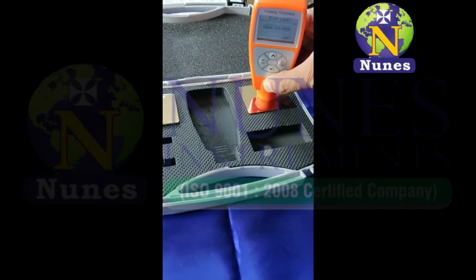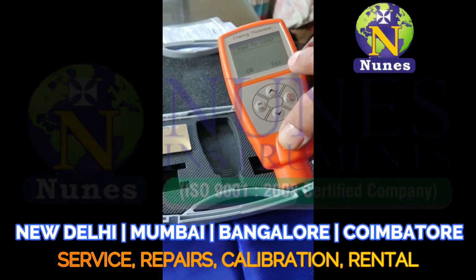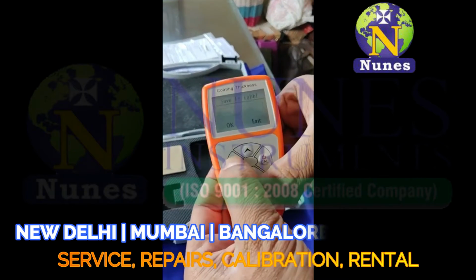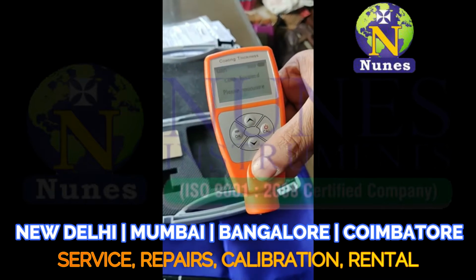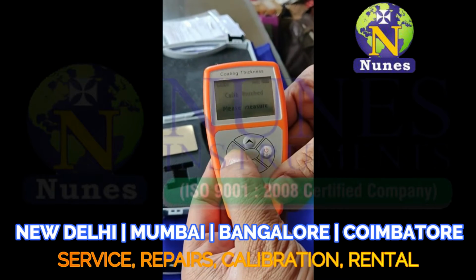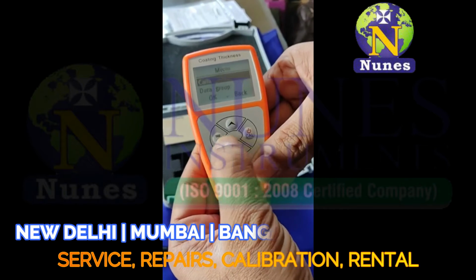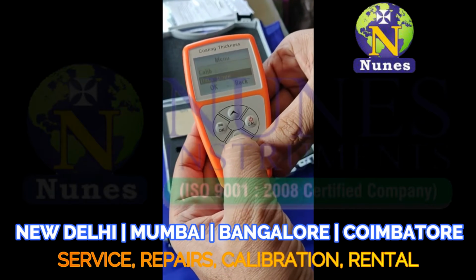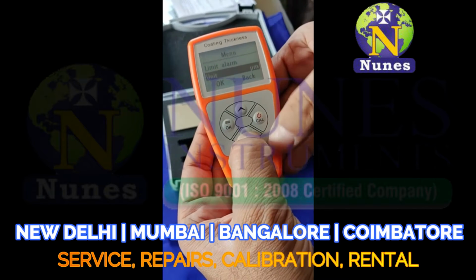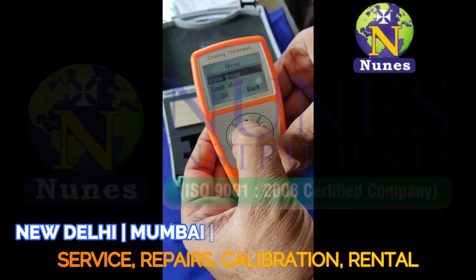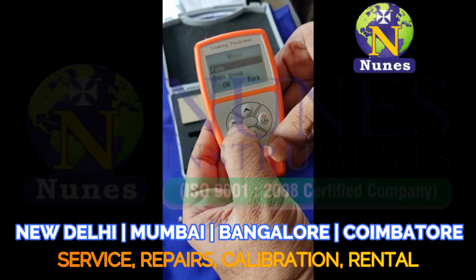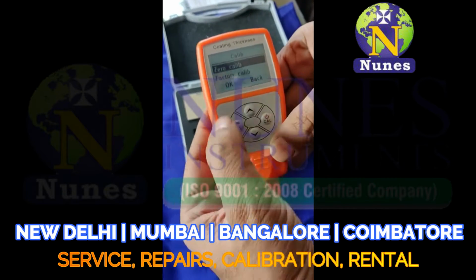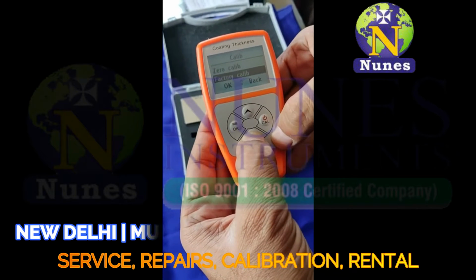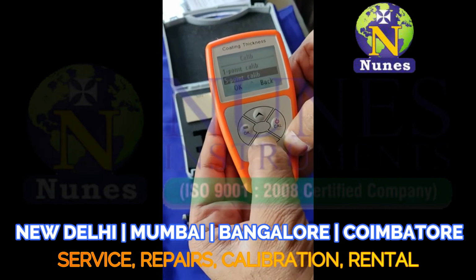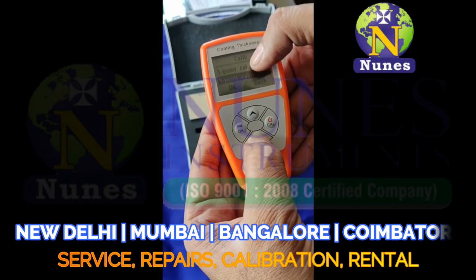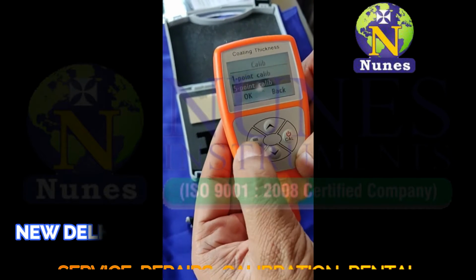So we lift probe, save. Okay, so the zero point calibration is finished, but there are 2-3 different types of calibration, so we'll explain them all. First is calibration data group, then limit alarm, unit, whether microns or mil, and about the company. So first we start with the calibration. When we press this, it says zero calibration, which we have already done. Then factory calibration if you want, first point calibration and 2 point calibration. We'll explain 2 point calibration so that 1 point calibration you can understand automatically.